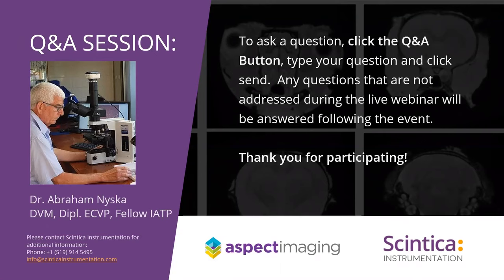There's a question about whether paraffin-embedded tissues can be used in the MRI system. Unfortunately no, because they would be completely dehydrated, and we do need the protons there to acquire the signal. That's where the fluorinert comes into play and helps us do all that imaging. Regarding resolution and scan times: at Duke, a whole rat brain was imaged at approximately 80 micron isotropic resolution with a scan time of about two and a half hours on a fixed sample.